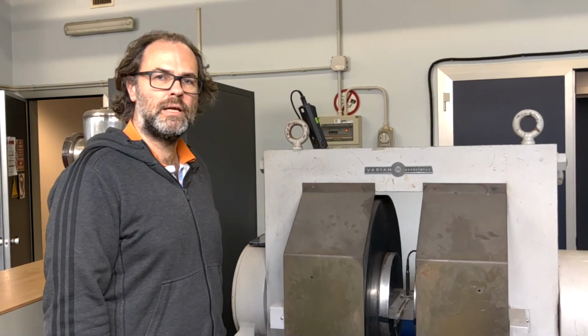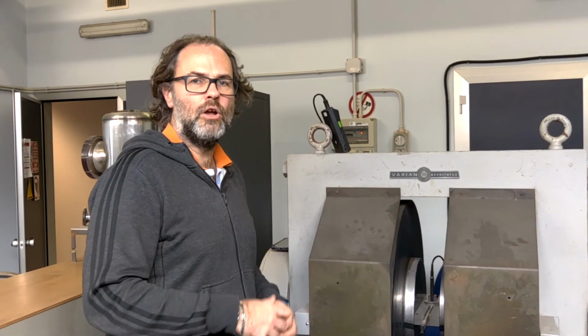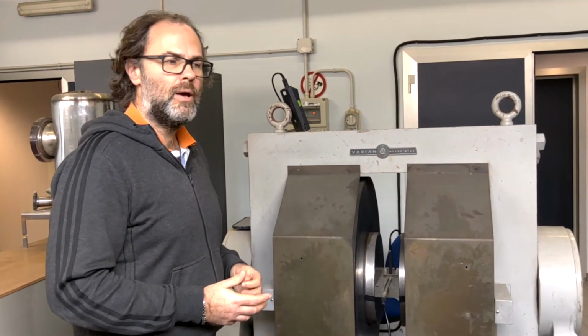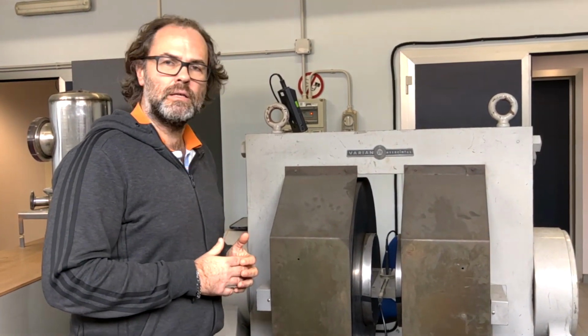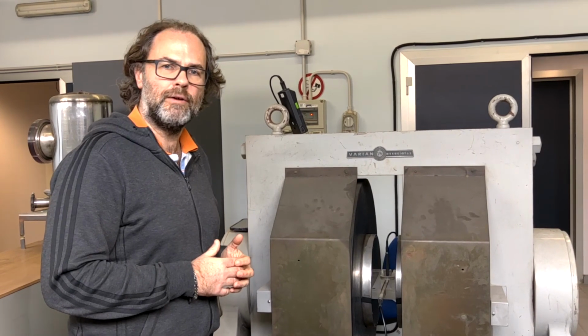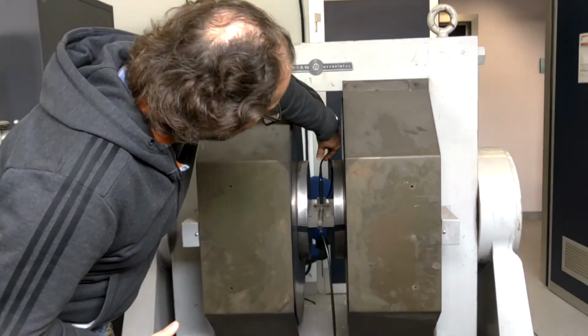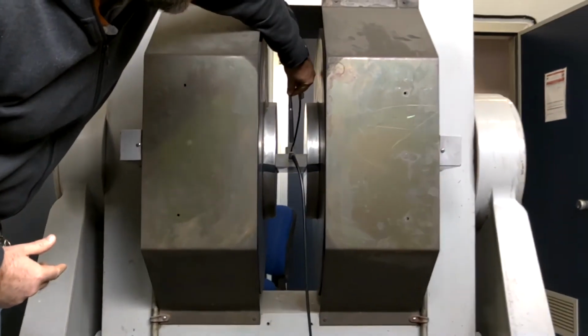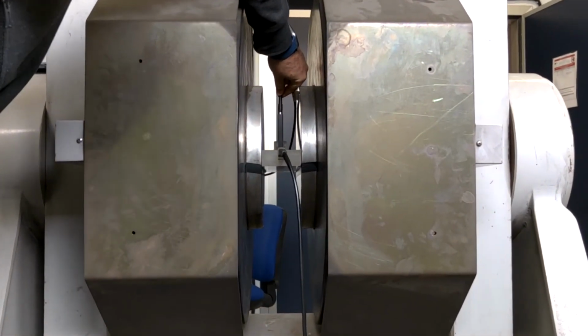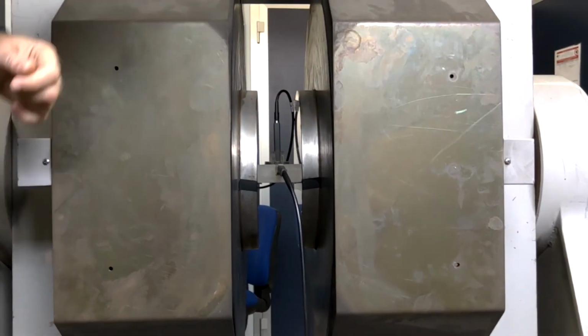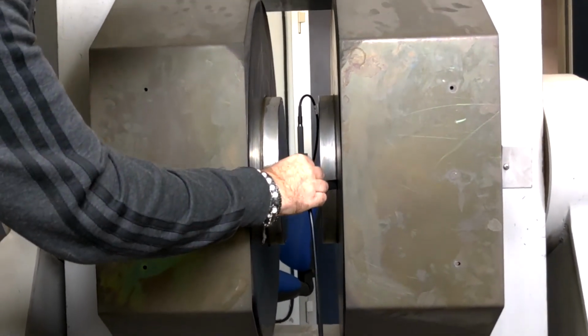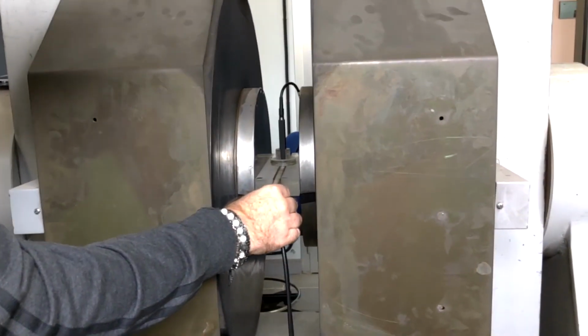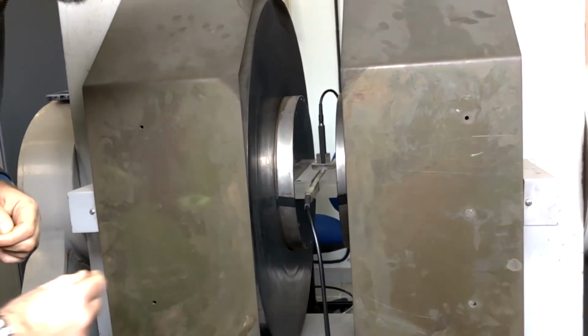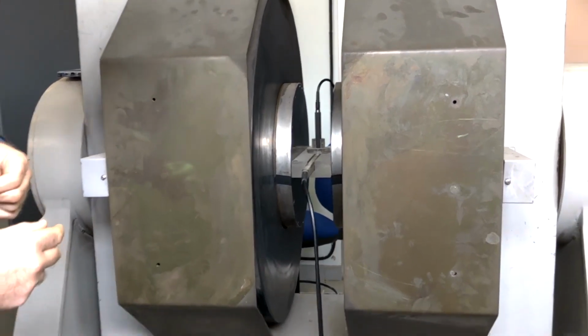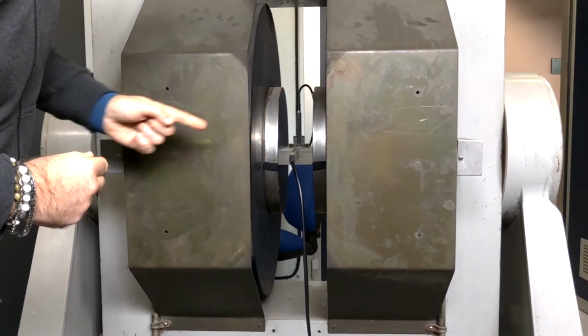The calibration is done by comparing the unknown probe that we want to calibrate with a reference probe that is based on the nuclear magnetic resonance effect. The unknown probe is this one and is placed in the middle of the gap of the magnet where the field is homogeneous. The same for the reference probe, the nuclear magnetic resonance one, which is placed in this direction, again in the middle of the gap. Both are transverse probes, so they are sensitive along the direction of the applied magnetic field.